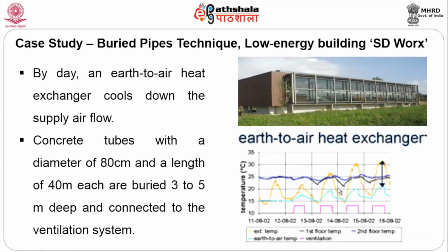Here we look at a case study again of buried pipes technique at SD Worx. By day, an earth to air heat exchanger cools down the supply air flow. Concrete tubes with a diameter of 80 centimeters and length of 40 meters each are buried 3 to 5 meters deep and connected to the ventilation system.